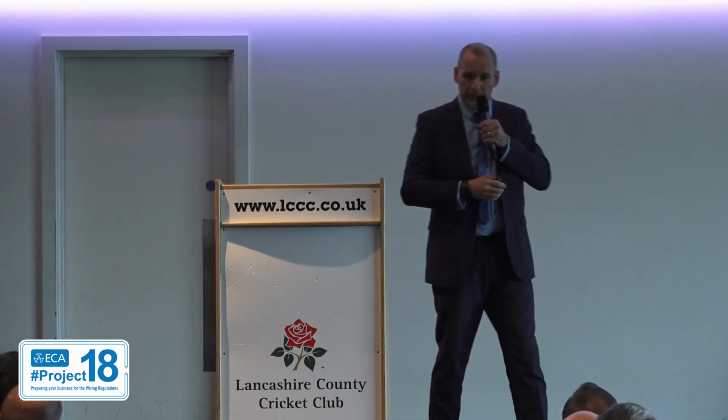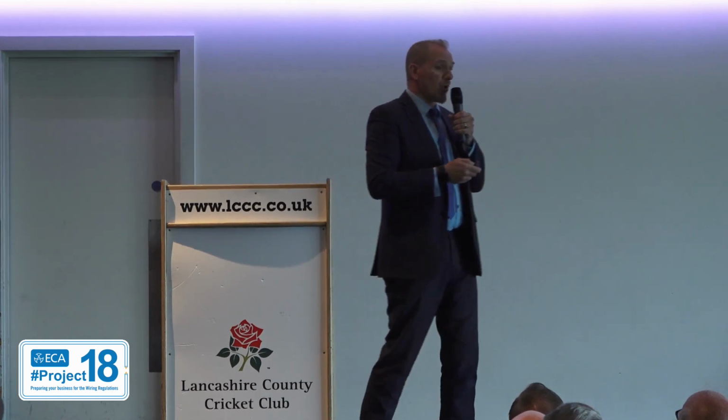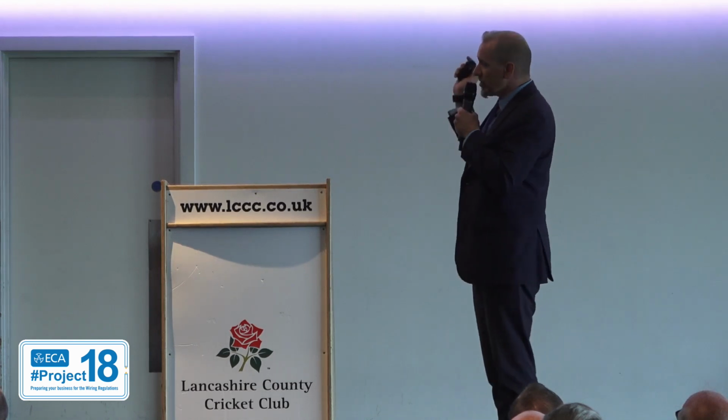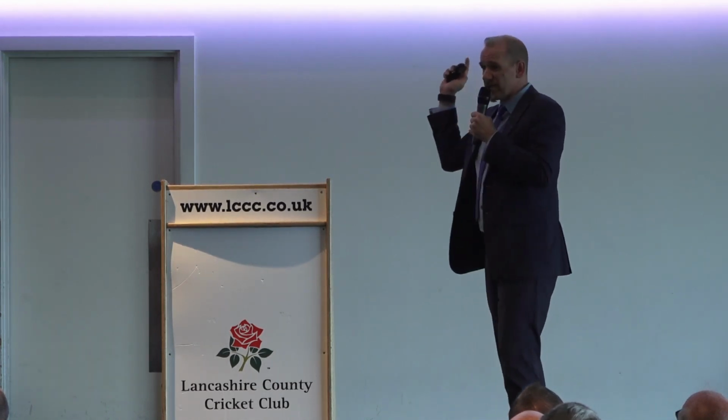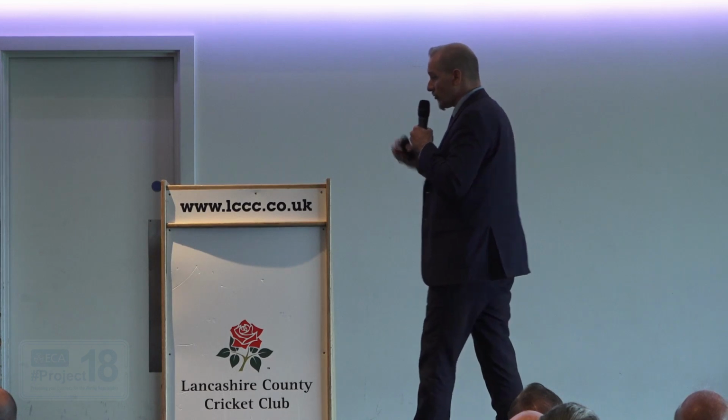So now if we have a fire situation, we still need to find an alternative way to leave the building, because my example again shows that we can't use the fire escape exits. However, those other zones now, we've got 3, 4, 6 and 7 operational, but the cables in there are now adequately supported against premature collapse. So, in extreme cases, when all of the exits are blocked, the fire crews might need to make their own entry point into a building, but they can do that in a much safer fashion now under this edition than previously, because when they come through the wall or the windows or whatever, all of the cables that are above their heads are now protected against premature collapse.